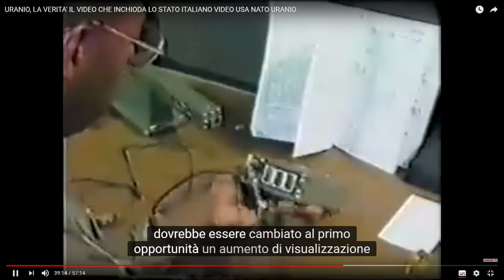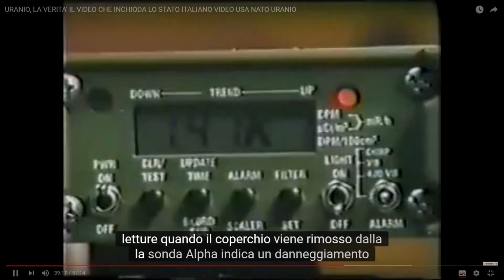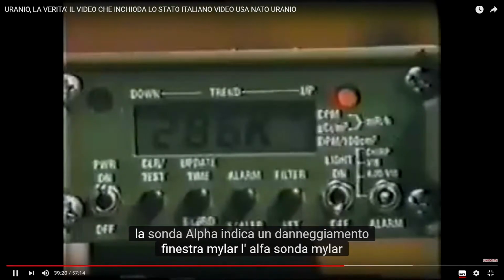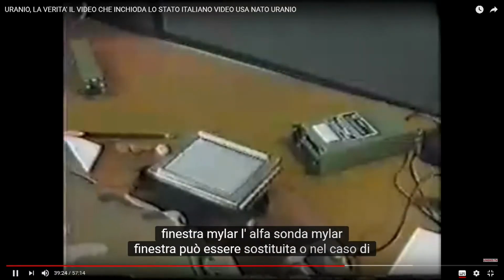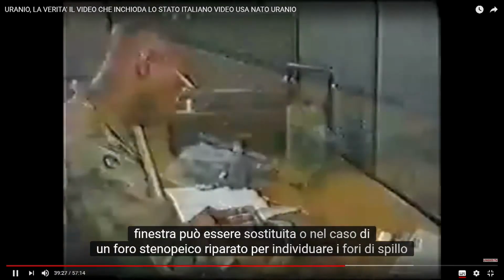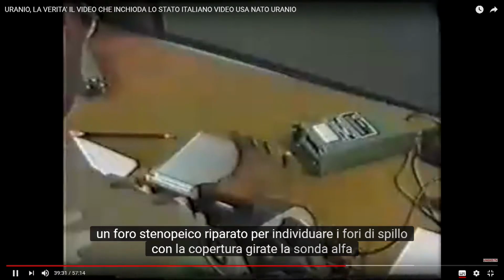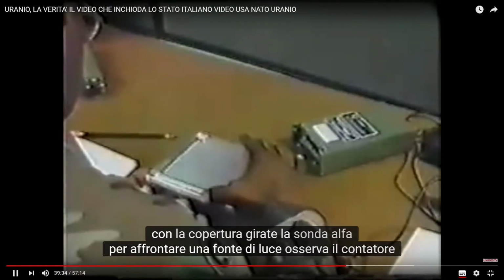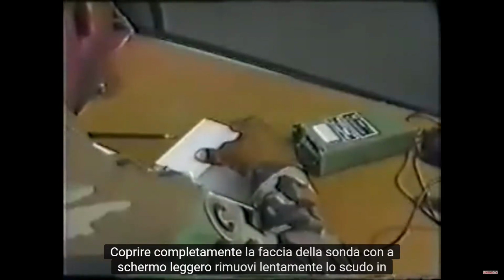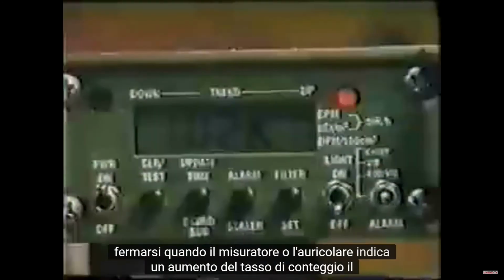and that they should be changed at the first opportunity. An increase in display readings when the cover is removed from the alpha probe indicates a damaged Mylar window. The alpha probe's Mylar window can be replaced, or in the case of a pinhole, repaired. To locate pinholes with the cover on, turn the alpha probe to face a light source. Observe the meter or listen on the headset and slowly remove the cover. Stop removal when the meter or headset indicate an increase in count rate. Now, completely cover the probe face with a light shield. Slowly remove the shield at a 90-degree angle to the probe cover. Stop when the meter or headset indicates an increase in count rate. The intersection of the access cover and light shield indicates the vicinity of the leak.